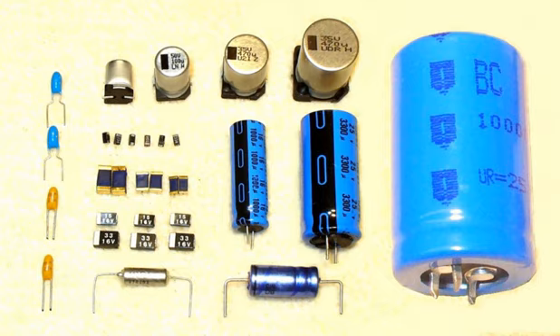The lifetime, service life, load life or useful life of electrolytic capacitors is a special characteristic of non-solid aluminum electrolytic capacitors, whose liquid electrolyte can evaporate over time. Lowering the electrolyte level influences the electrical parameters of the capacitors. The capacitance decreases and the impedance and ESR increase with decreasing amounts of electrolyte.